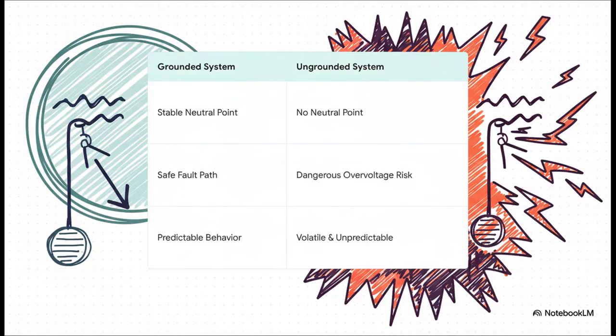This comparison lays it all out. A grounded system is stable and predictable. But an ungrounded system, which you might find in some older industrial setups called delta-connected systems, is a complete wild card. With no path to ground, if there's a fault on one wire, the energy has nowhere to go. It surges back into the system, creating a massive voltage spike, a dangerous overvoltage on the other two wires. The whole thing becomes incredibly volatile.